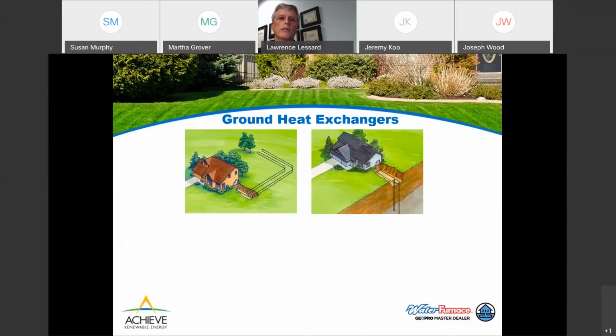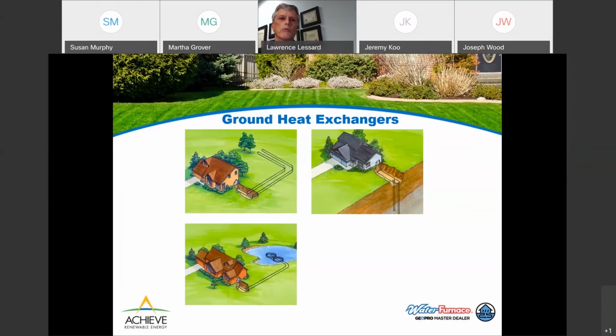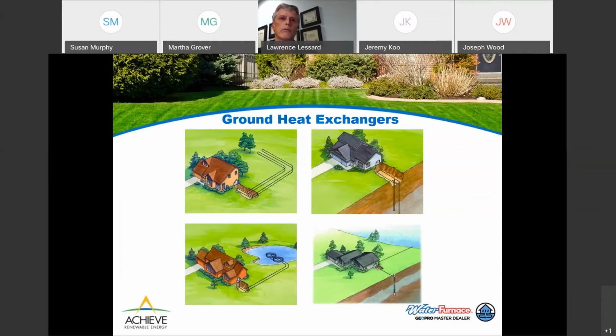The second slide that's come up is a vertical closed loop, where we would do the same heat exchange, but do it vertically with those borings being installed with a drilling rig. There's no surface exposure of that drilling after we're done, and everything's backfilled. The third slide that came up shows an exchange with a pond. That's also popular in other parts of the country, very difficult to permit in Massachusetts with conservation requirements and most ponds being owned by municipalities, not the people with frontage.